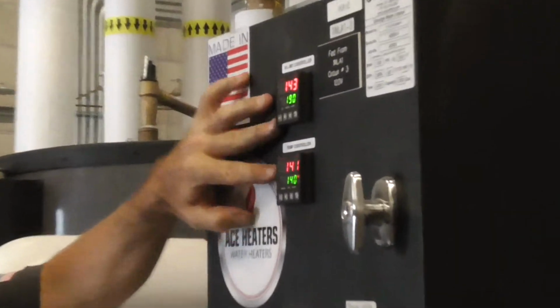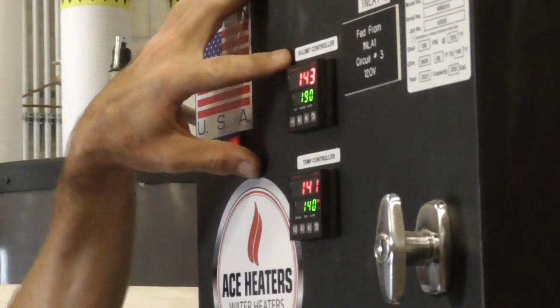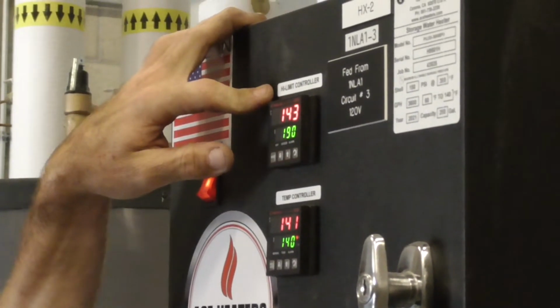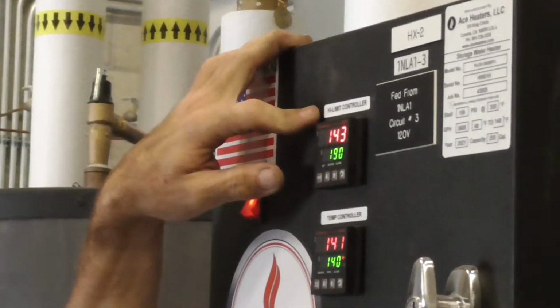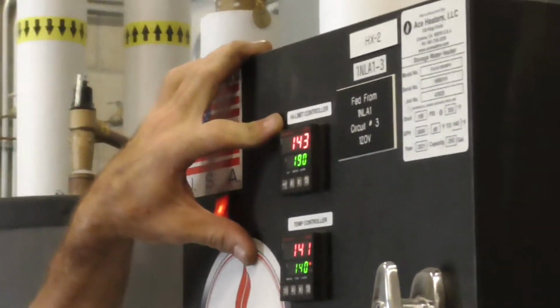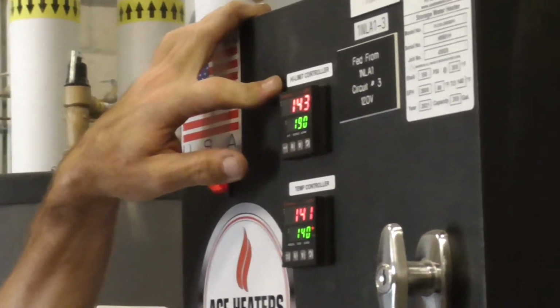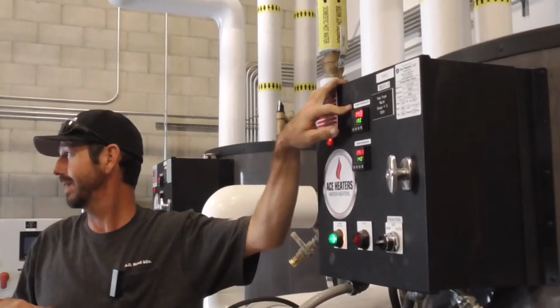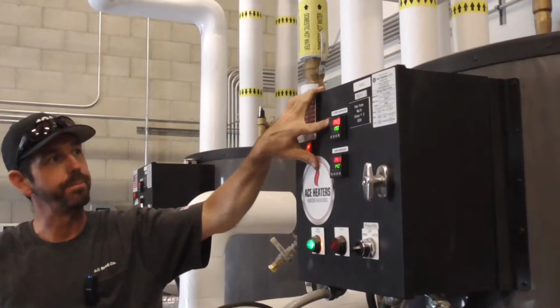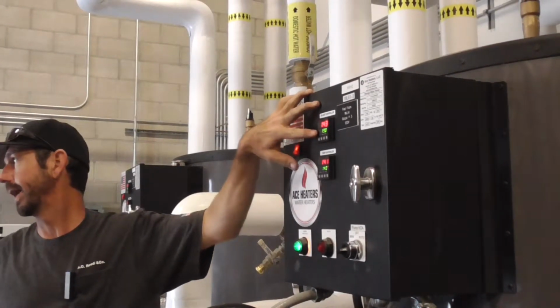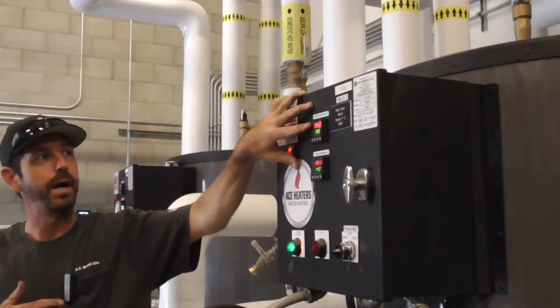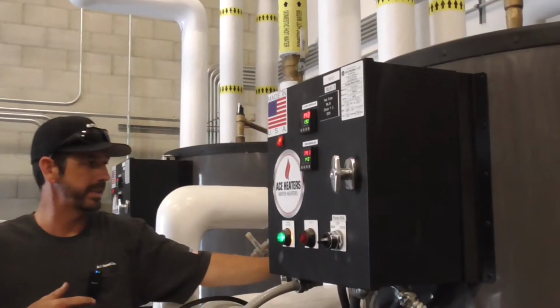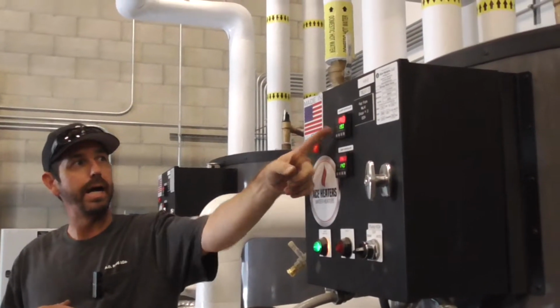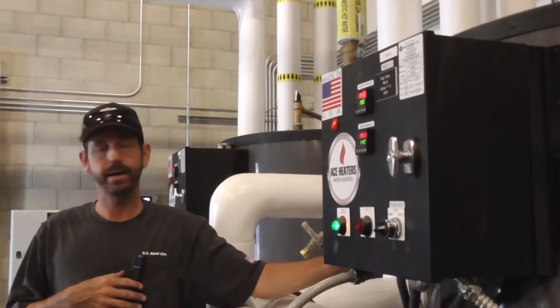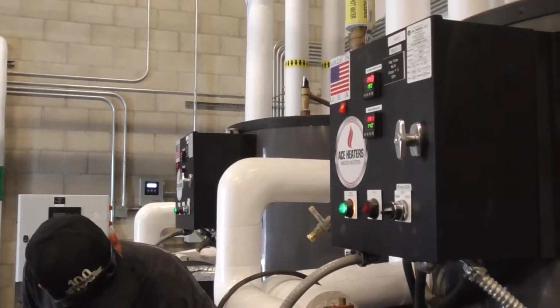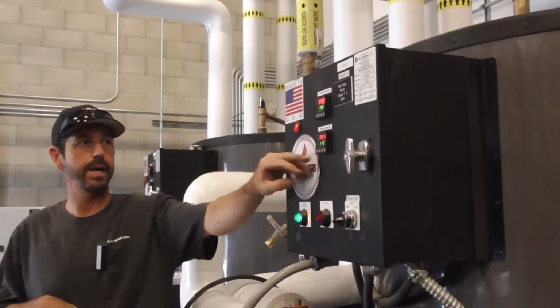So these two controllers right here, we have our high limit controller. This high limit controller would be more if you're like high temp water or steam, and you can get into boiling temperatures. The warmest I've ever seen the water come over here is like 160 on the plant. So the set point's 190, right? We should never get close to that. This will always read a little bit higher because it's up higher on the tank, okay? So our high limit controller is the upper sensor over here, and then our controlling temperature sensor is the box down there, which is the lower controller, okay?